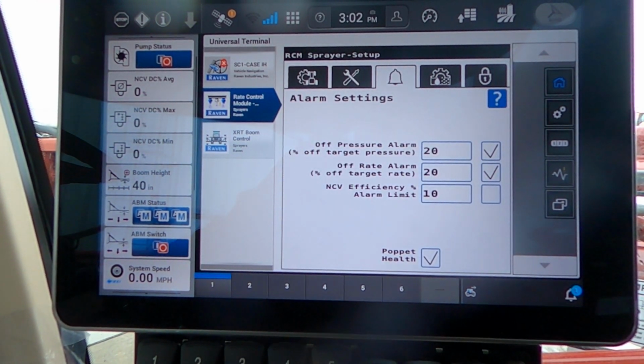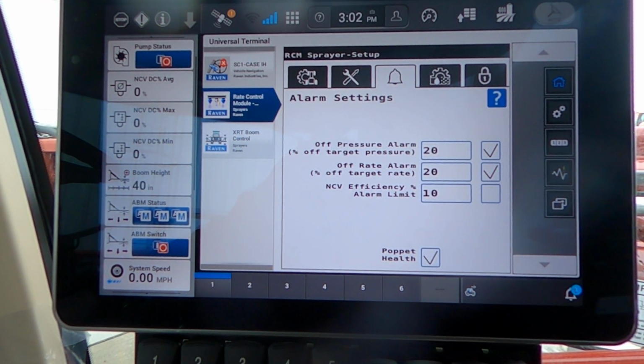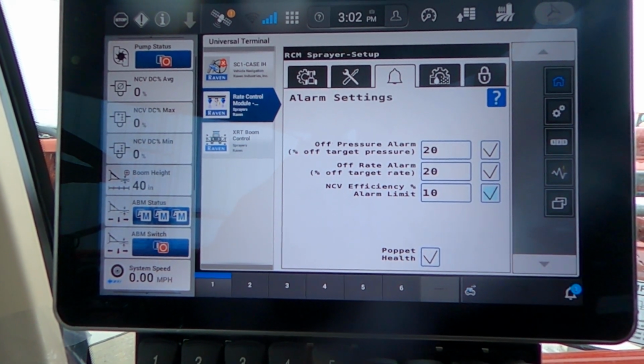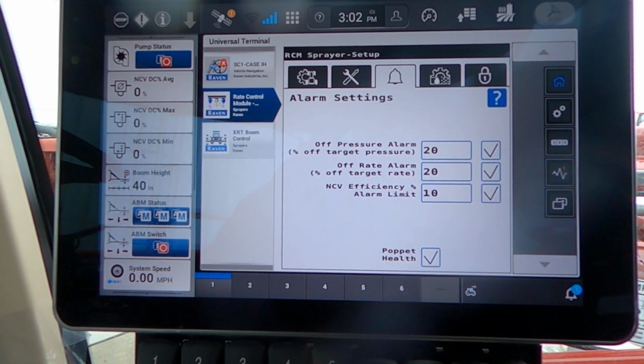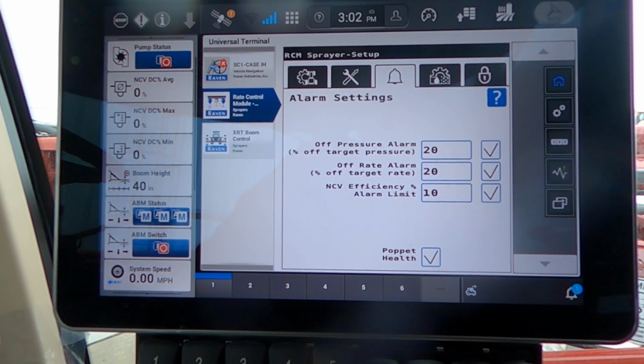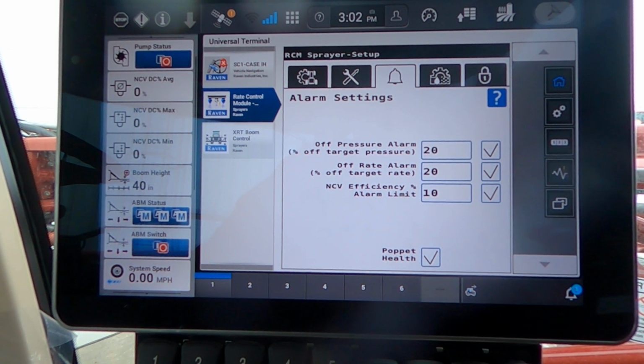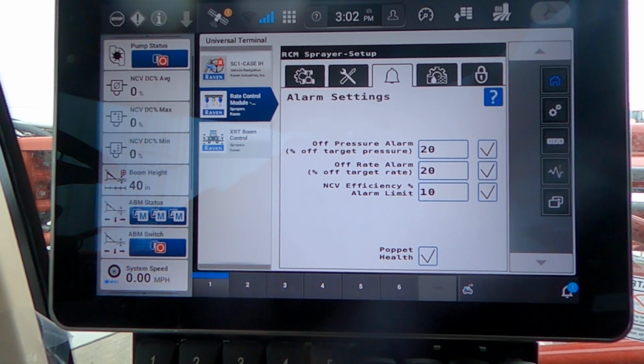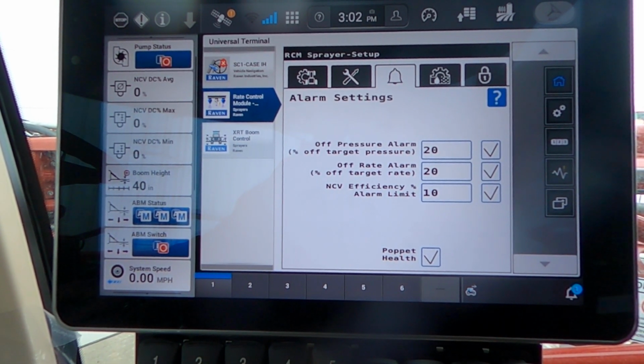If we go to the bell, this gives us alarm settings. So if we're off pressure alarm, if we're off 20%, it'll beep. Off rate 20%, it'll beep. NCV efficiency 10%, that is normally defaulted as not checked. If you turn that on, NCV efficiency basically will tell us if we have plugged filters. If our NCV efficiency starts running low on the display, we might have plugged filters. We're not getting enough product, we're under applying. If we're running over, that could indicate a leak somewhere on the machine. So it's nice to have that NCV efficiency turned on. Poppet health should always be turned on. That'll tell you if you have stuck poppets.